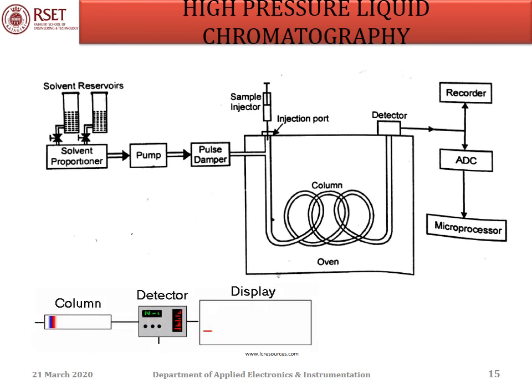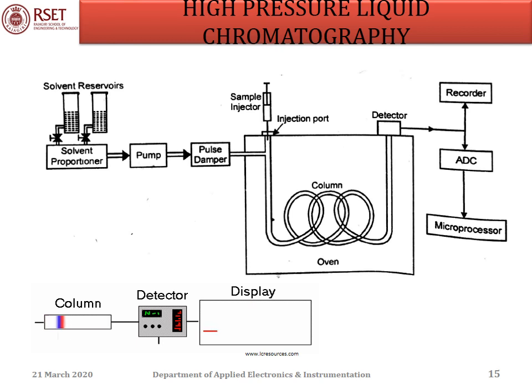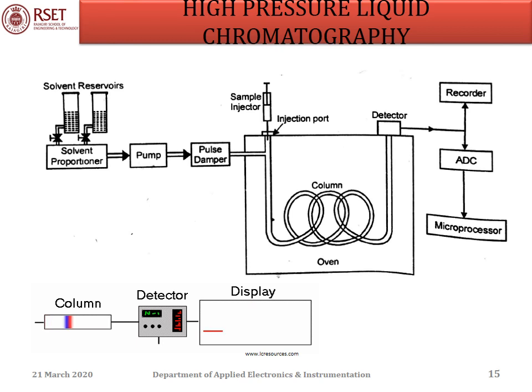The mobile phase liquid from the solvent reservoir is delivered to the column by a pump. The pumping system must be pulse-free, or a pulse damper must be installed to avoid instability in the detector. Sampling valves or loops are used to inject the sample into the flowing mobile phase. The sample dissolves in the mobile phase, and the different species are separated from each other while passing through the column. The detection system senses these components as they elute and produces a signal proportional to the amount of solute, which is applied to the recorder or microprocessor for further processing.